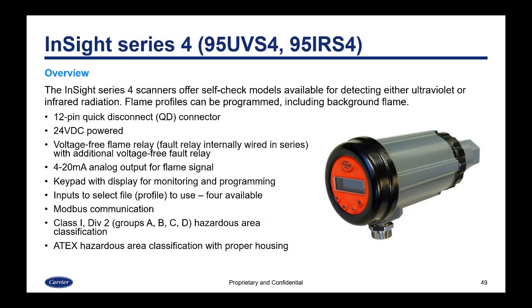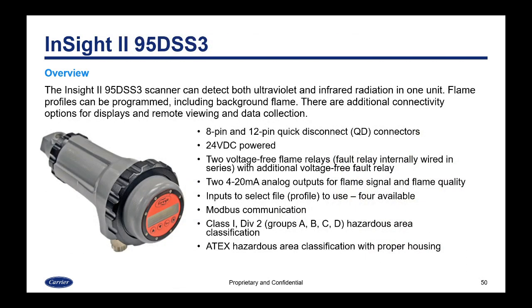InSight Series 4 is similar to the InSite we just covered and has all the same features. The InSight II has two connectors — an 8-pin and a 12-pin quick disconnect — because it has two flame relays instead of one. It still has the fault relay and offers two 4 to 20 milliamp analog outputs — one for flame signal and one for flame quality. It still has four available profiles, Modbus communication, Class 1 Div 2 as standard, and ATEX hazardous area classification available with proper housing.